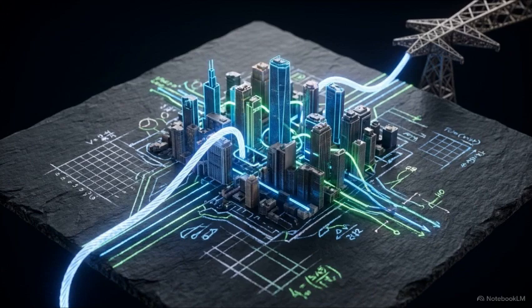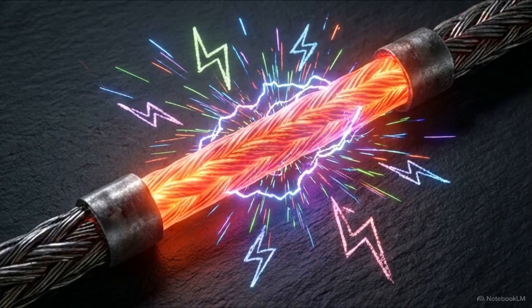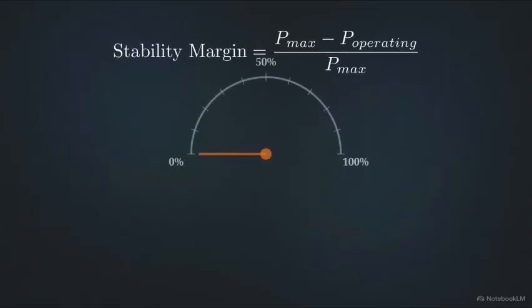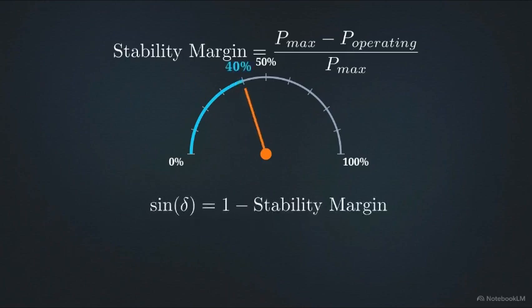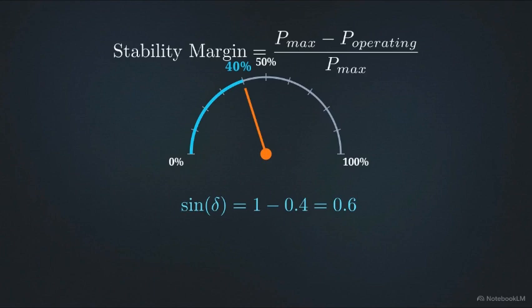Calculating a maximum capacity is a theoretical exercise, but pushing a physical grid to that absolute ceiling guarantees an eventual system collapse. This gauge visualizes the stability margin, calculating the breathing room between active power and absolute peak capacity. If operators mandate a 40% margin to absorb disturbances, this buffer directly dictates the maximum safe operating load angle.